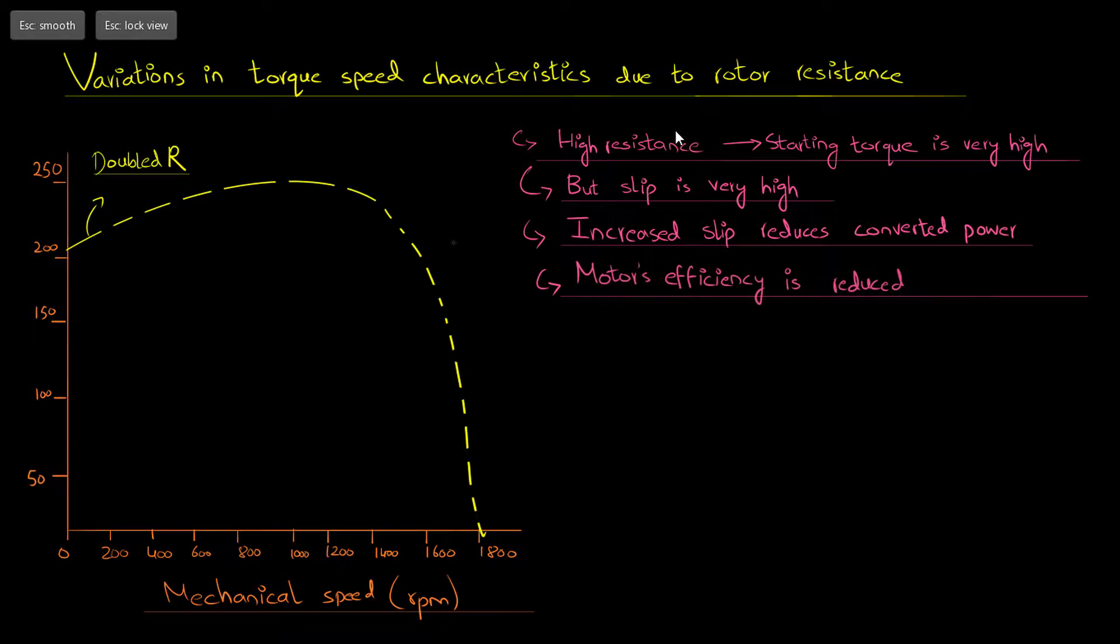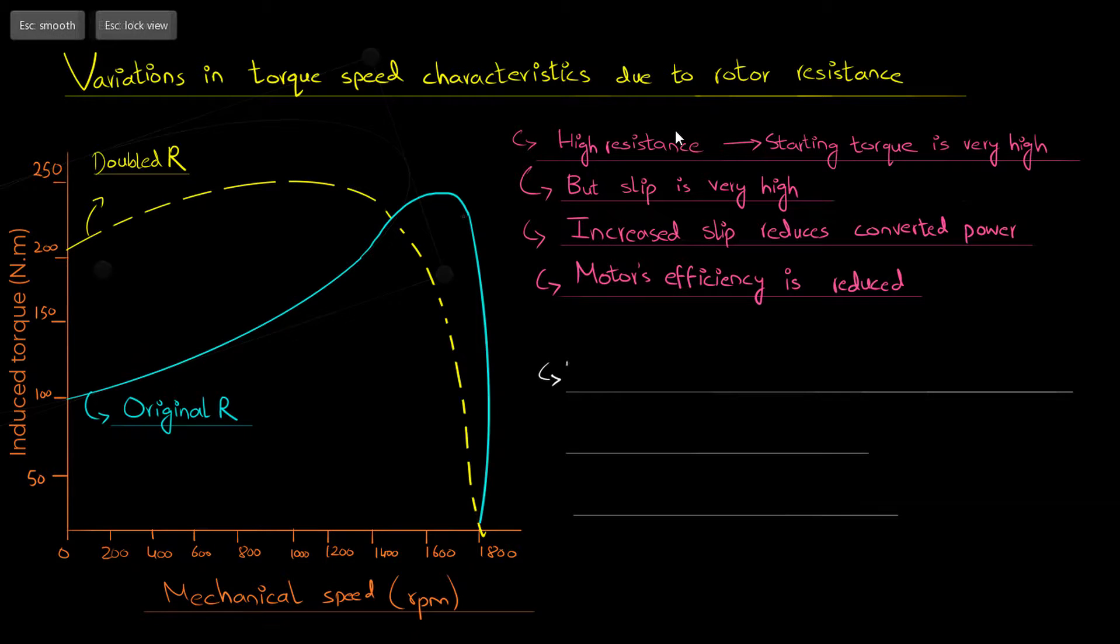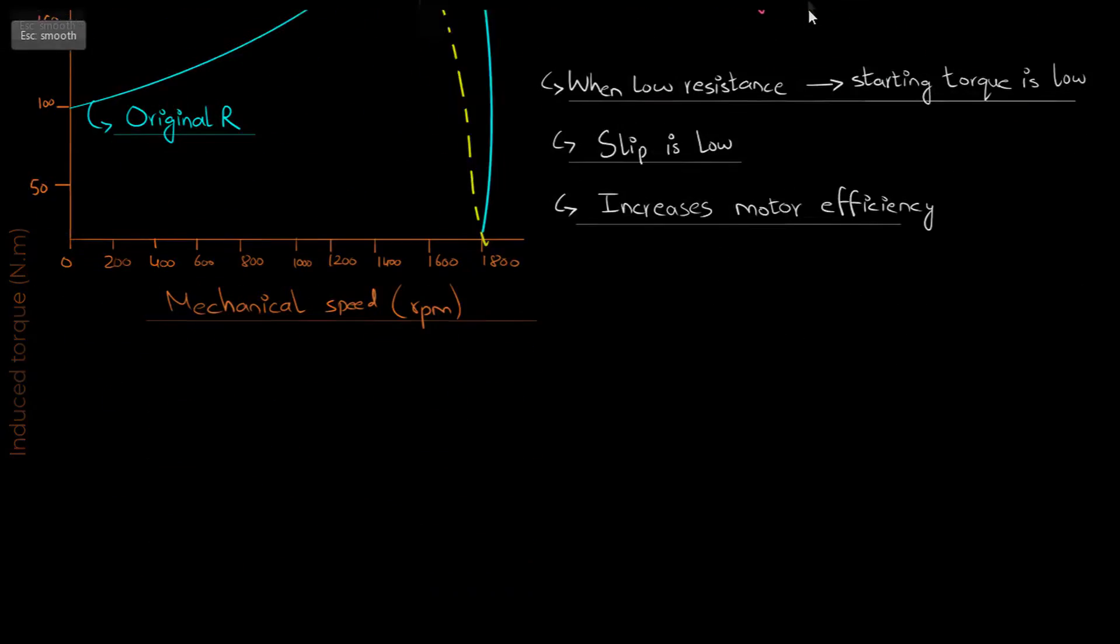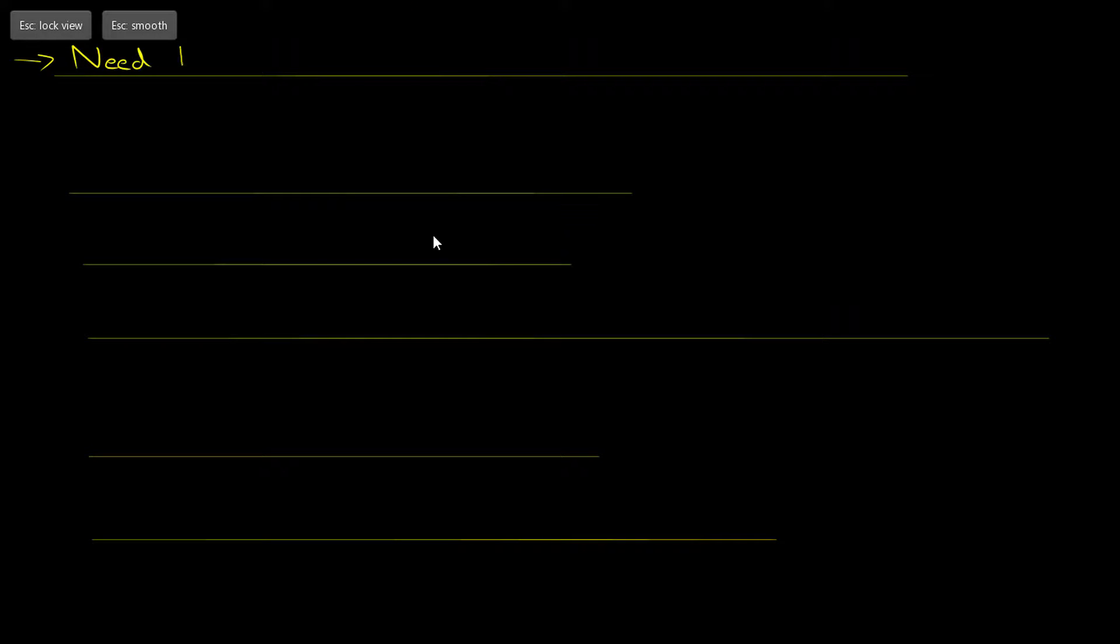Opposite to this scenario, when the rotor is designed with a low resistance, then the motor's starting torque is low and the slip is also low in normal operating conditions, which increases the motor's efficiency. Both of these scenarios are illustrated in this figure.